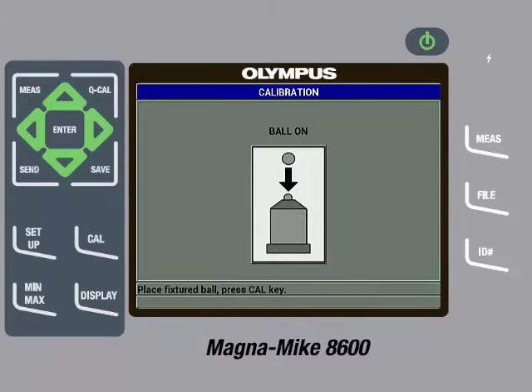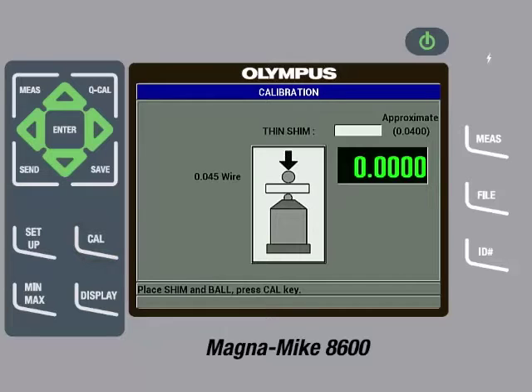Then, place the fixtured wire on the probe and gently pull down on the sides of the fixture to ensure the wire is in contact with the probe tip, then press the Cal key. After processing, the gauge will display a 0 value. We can now remove the wire and fixture. The gauge will then ask for a thin shim and call out an approximate thickness. The thin shim called out for the wire target being used is 0.0400, or if you are using metric units, it would be 1.016.